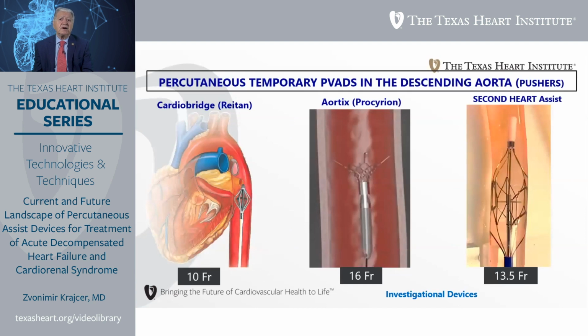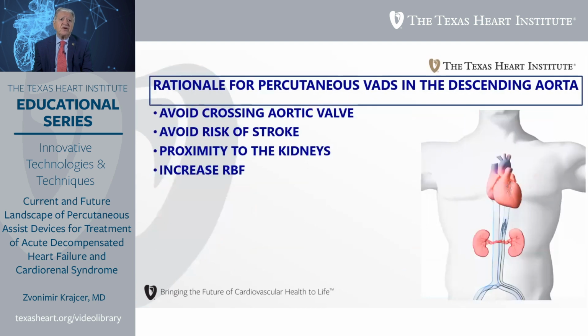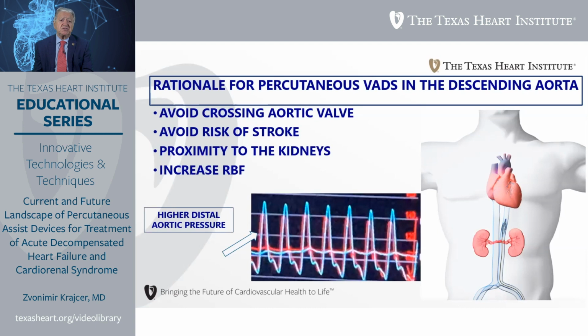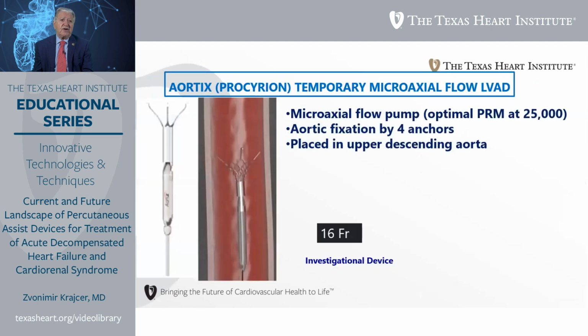Now, an interesting group of devices, which we call pushers, are placed in the descending thoracic aorta, and they include CardioBridge, Aortix, and Second Heart Assist device. All of those devices have certain benefits, and the rationale for percutaneous use of these devices is to avoid crossing the aortic valve, so we avoid risk of stroke, and it's located in proximity to the kidneys to improve the renal blood flow. And as we can see, this is based on differential of the pressures between above the device and below the device, where the pressure below the device is 10 millimeters of mercury higher than above the device.